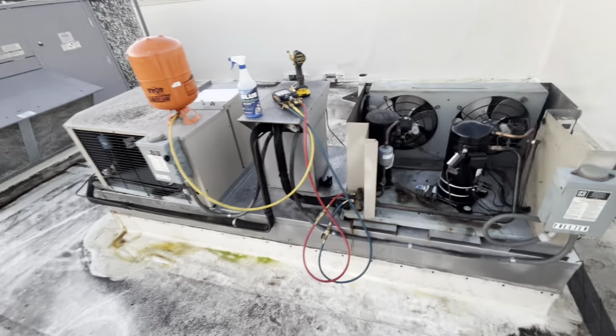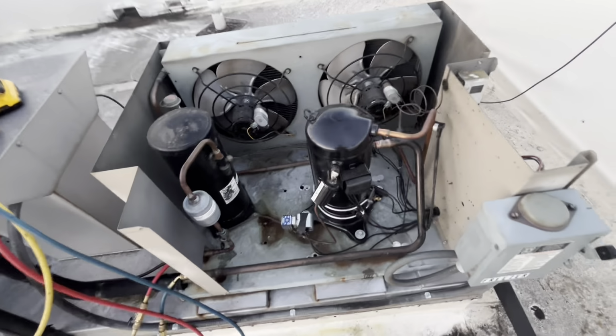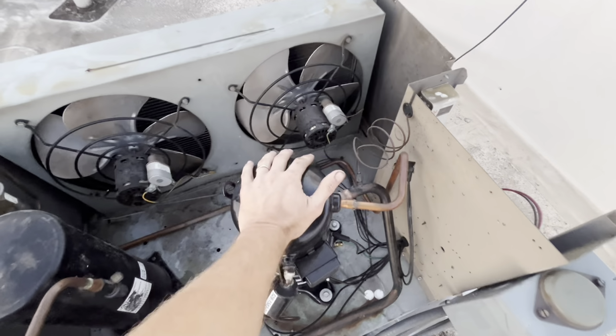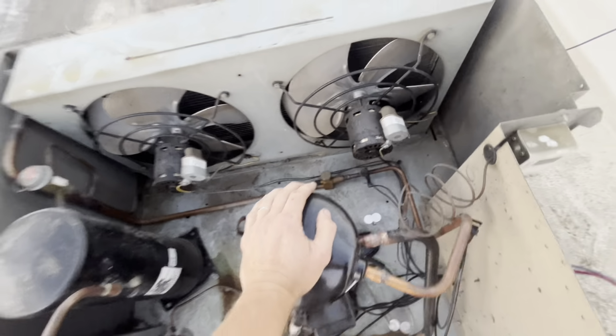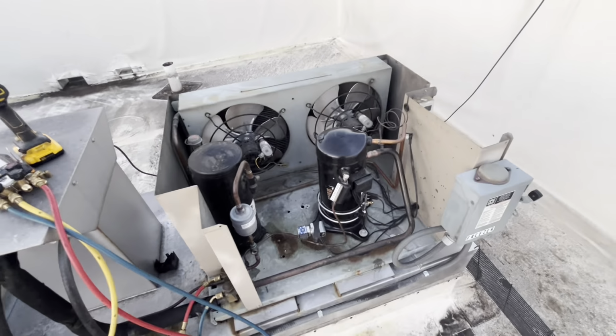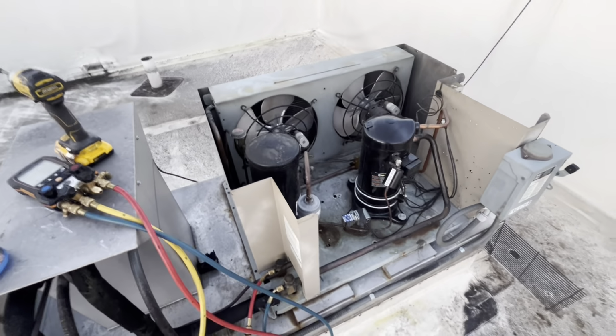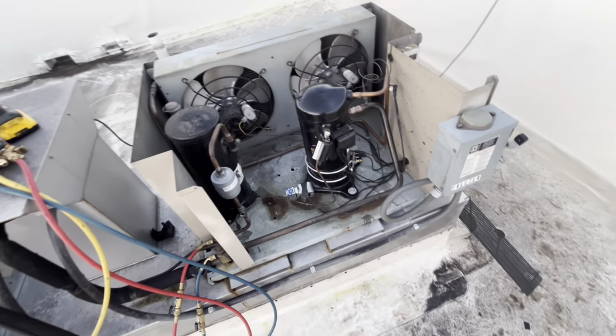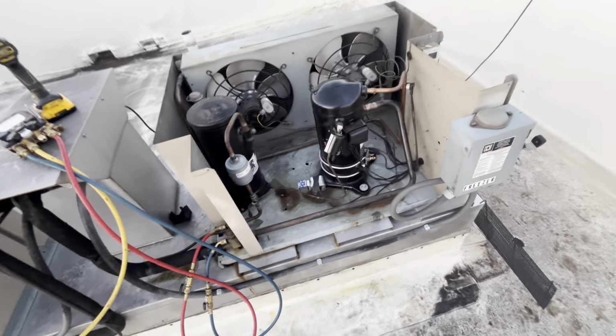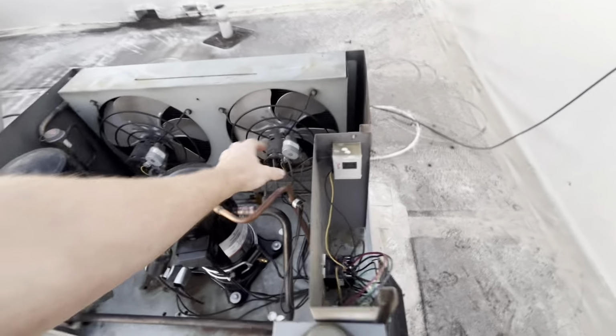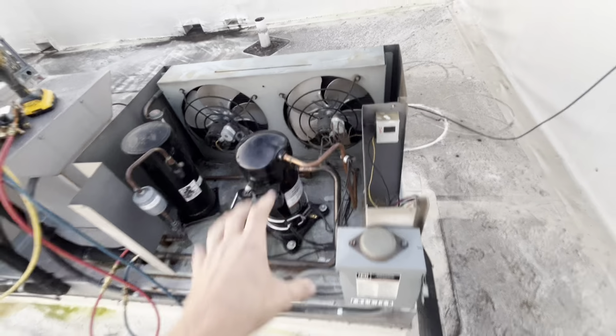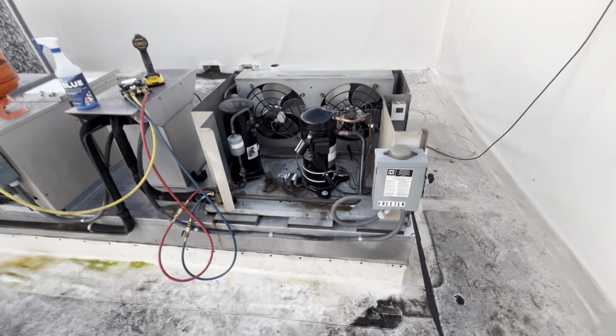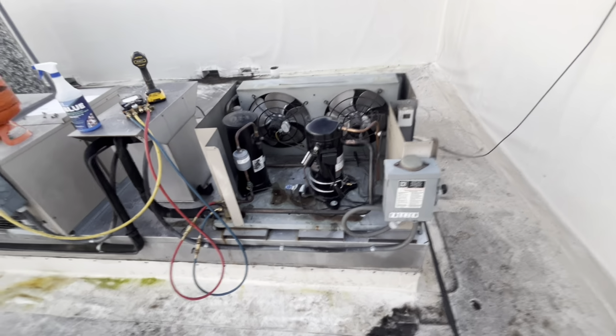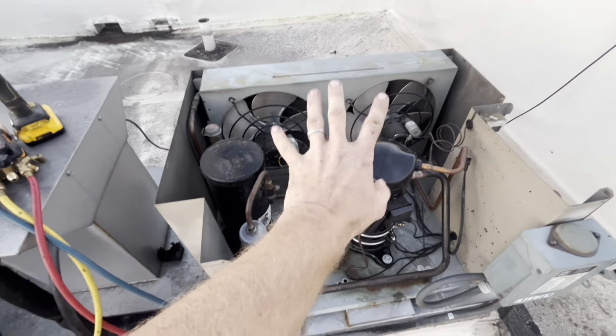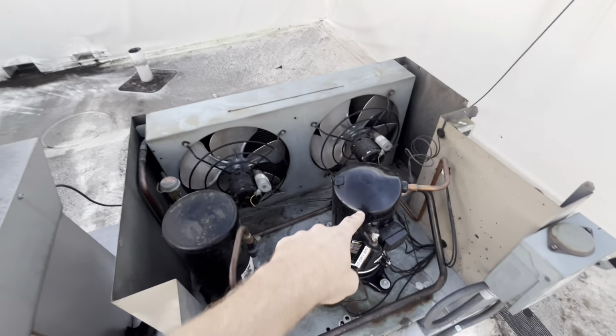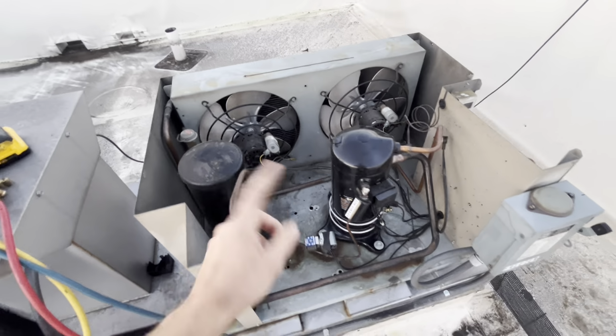Good morning. This is a walk-in freezer. I replaced this compressor a few months ago. Oh, short to ground. So, walk-in freezer, liquid injector, kind of a funny setup. They called last night, and the owner's very involved. He said it was short cycling, that up here on the roof the fans were coming on, that the fans and compressor were cycling on, off, on, off, on, off.